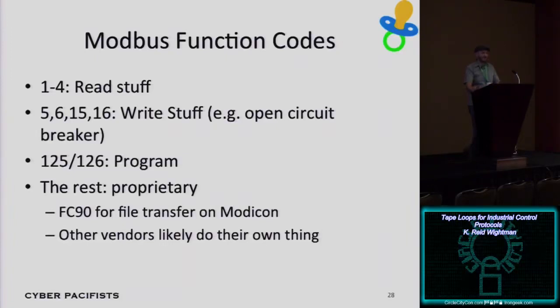For some background, Schneider bought Modicon years ago, and Modicon are the people who invented the Modbus protocol. So if Schneider doesn't use function code 125 or 126 for ladder logic upload, probably nobody is going to. Schneider uses function code 90 for ladder logic upload and download, but you can also do arbitrary file transfer with it.